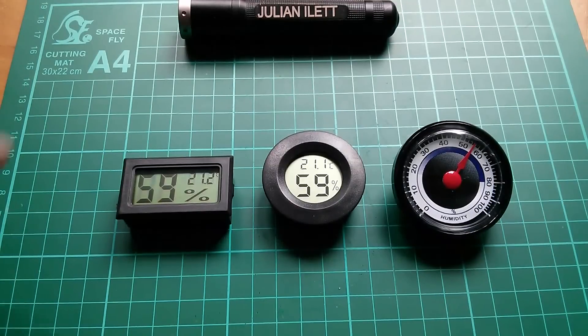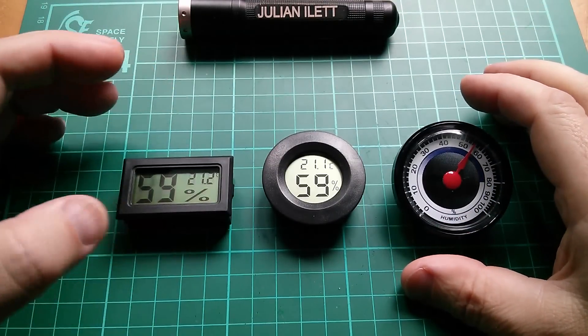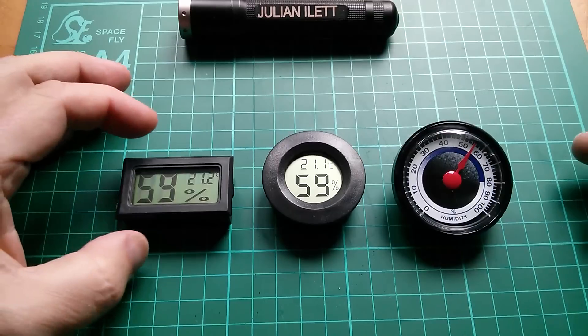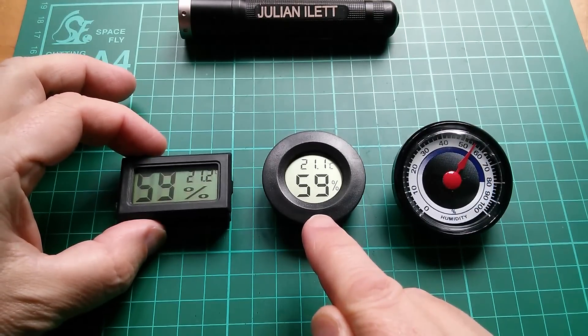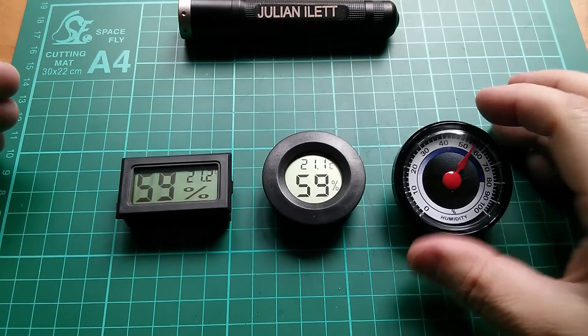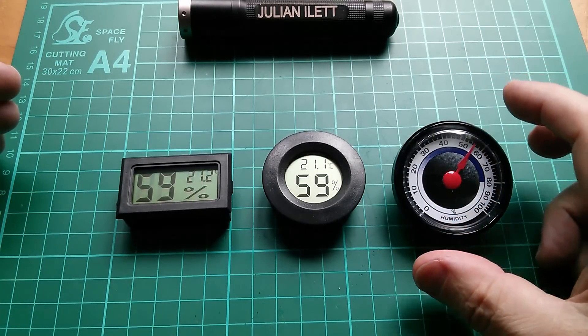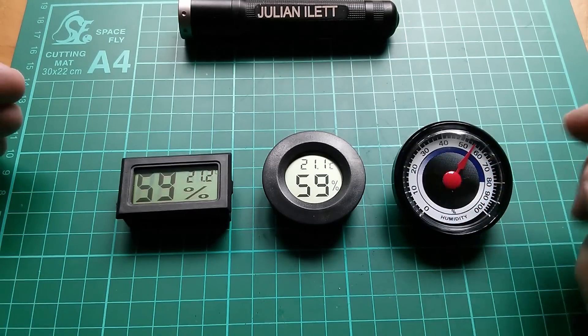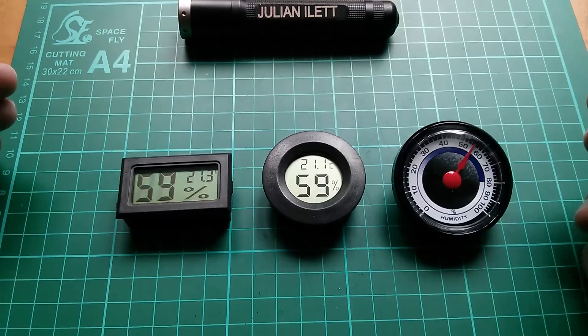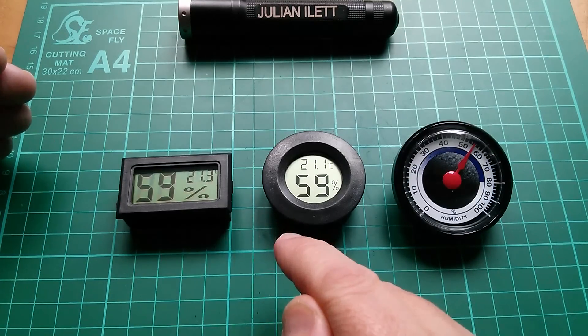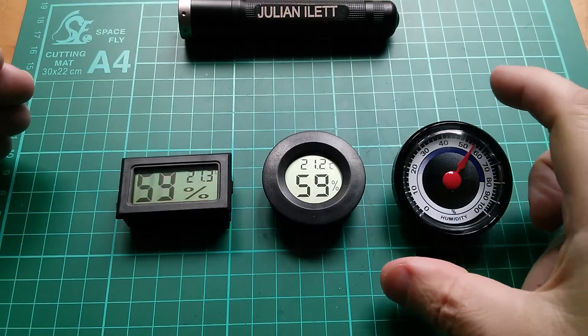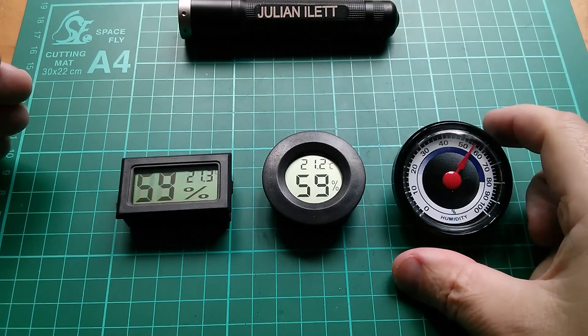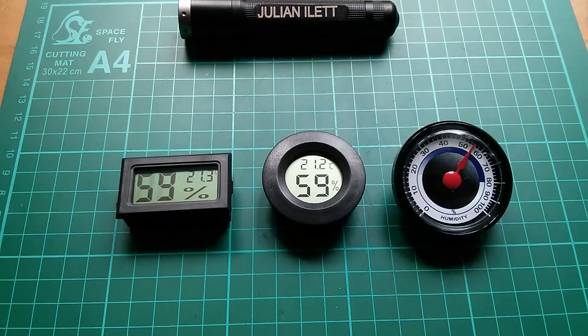Good morning all. Humidity meters or hygrometers. I've got three here. I've got a little electronic square one, electronic round one, and a mechanical round one, which is just a coil of some sort of material, I'm not quite sure what, attached to a needle, and then there's a paper dial underneath. Now they're all in reasonably good agreement, particularly the two electronic ones, 59 and 59, and this one is reading about 55, so that's not quite so good.